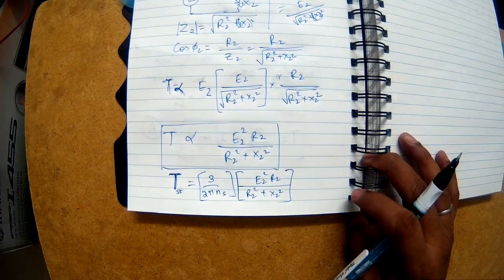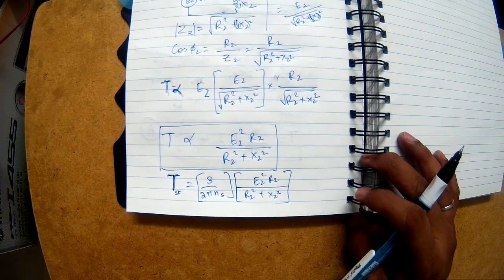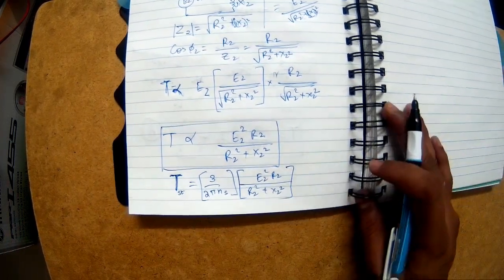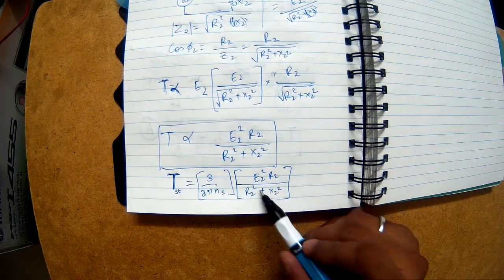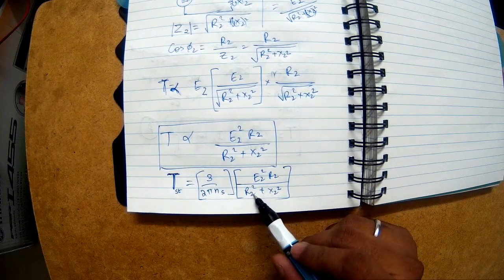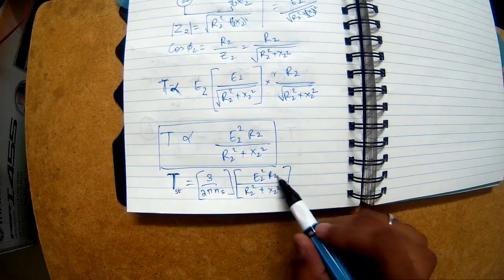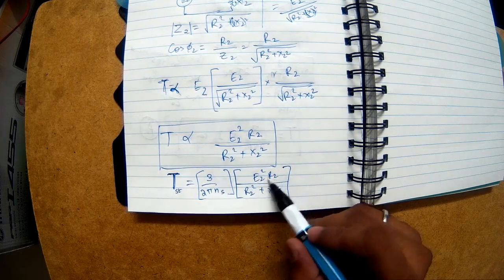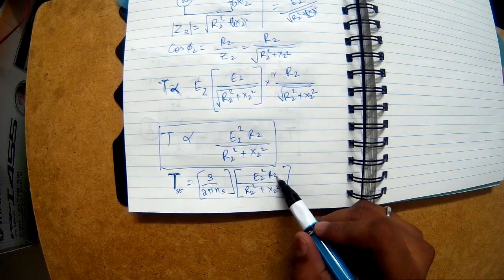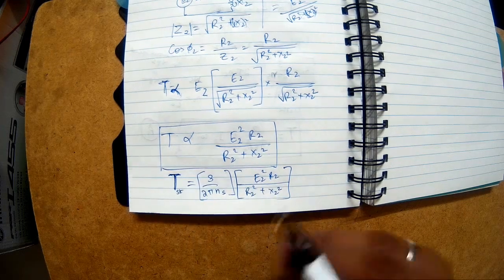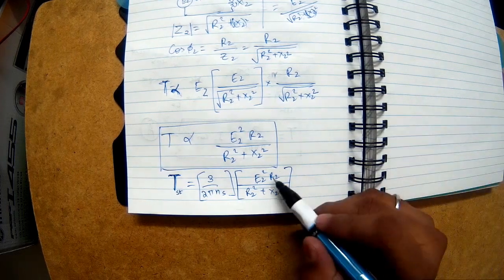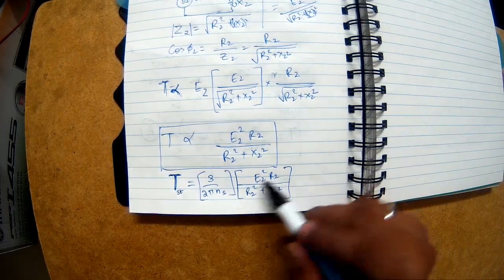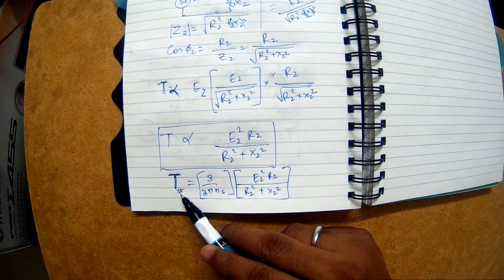Now shall we make a quick comment about how to increase or decrease starting torque. For example, consider that R2 is very small compared to X2. In fact, which is the case, because the squirrel cages have very thick copper bars and the resistance is very small. So if R2 is almost 0, very very close to 0, the starting torque is 0, therefore the motor will never start at all. The motor is always remaining stationary. So definitely some small resistance is required for some small starting torque to be present.